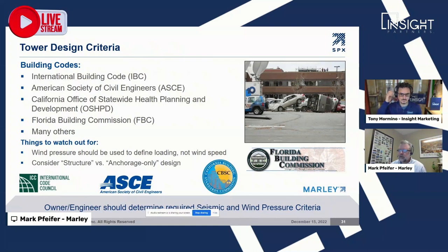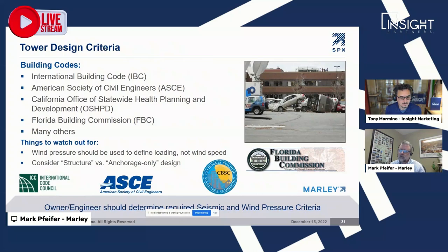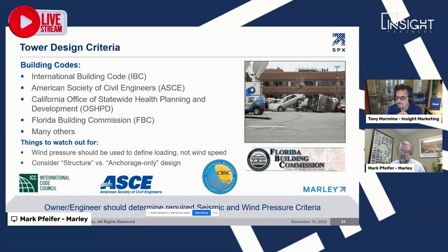There are other building codes and design criteria to include: IBC is common. OSHPD applies to California healthcare requirements. Florida building code does come up for those designing in the Florida region — they have high wind requirements. We ask that design engineers determine the wind pressure for manufacturers to meet. Sometimes we get vague wind speed requirements that aren't definitive, which means manufacturers have to make their own assumptions and results may vary. If you provide a specific wind pressure, we can clearly state which model meets your requirement.